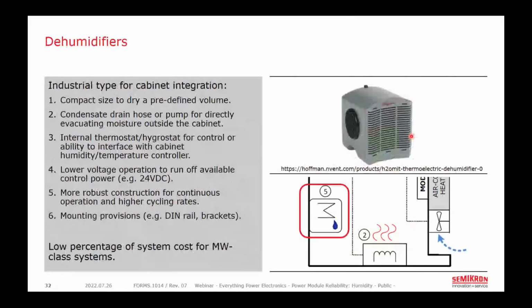For actually removing the water vapor from mostly sealed cabinets, a dehumidifier is used. And these are industry-specific units that use the same process as commercial dehumidifiers you might use in your basement to condense water vapor into a liquid, but they have some special features such as the ability to run off of 24-volt DC control power, mounting for DIN rails, or integration with a system hygrostat or controller. And these systems don't have tanks to hold the water, but rather a condensate hose that you feed out of the cabinet. And some of you might balk at the cost of a dehumidifier or a cabinet heater, but these tend to be relatively inexpensive compared to the cost of the system they are trying to protect.